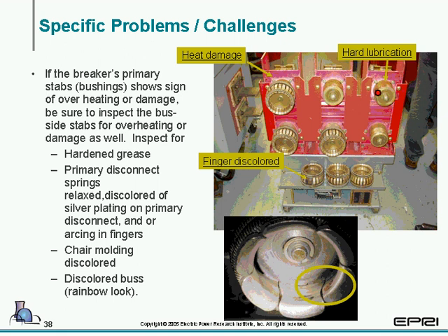We removed the primary disconnects and found hard lubrication on the upper 3 leads. If you look here on this finger assembly, you'll see that one of them is actually black in color, where all the others are silver. And we'll be taking a look at those in another slide in a moment. In the very bottom one, you'll see a sputtering contact where you could actually see the copper underneath, and it was very jagged. It looks like pitting. All right, we'll take a look at each one of these a little closer.